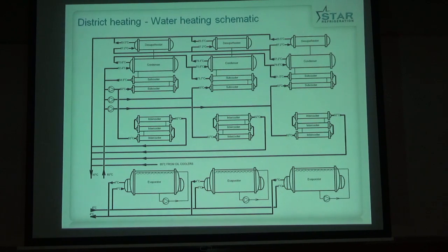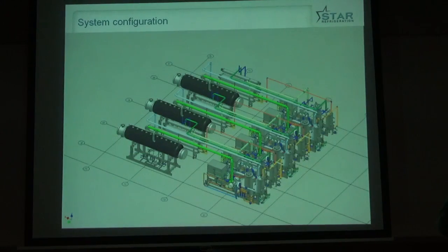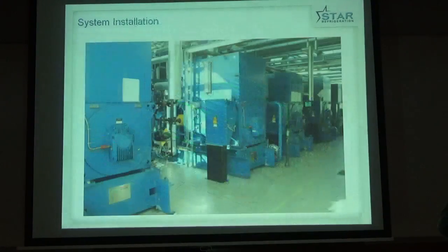the desuperheaters. There's also a bit that's not shown here: we use water-cooled electric motors, and the inefficiency of the electric motor also eventually ends up in the district heating loop. So even the energy that we would have lost into the air is scavenged and recovered and put back into the system. And this gives us a flow at 90 and a return at 60 degrees. So a schematic of what it looks like.